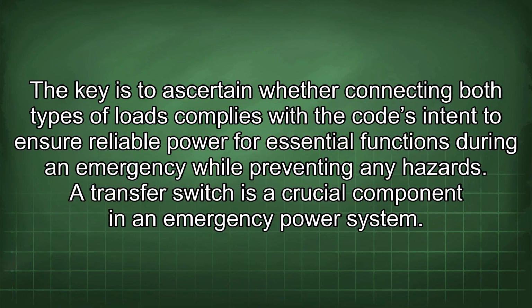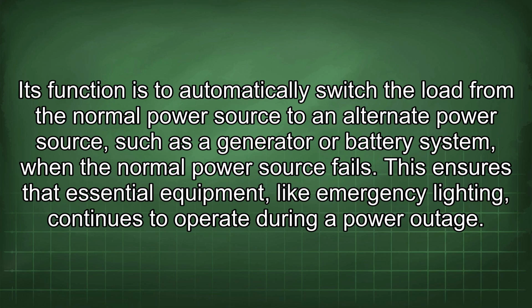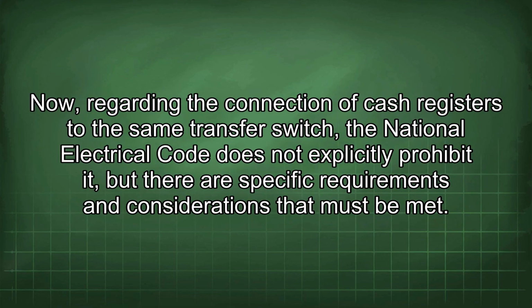A transfer switch is a crucial component in an emergency power system. Its function is to automatically switch the load from the normal power source to an alternate power source, such as a generator or battery system, when the normal power source fails. This ensures that essential equipment, like emergency lighting, continues to operate during a power outage. Now, regarding the connection of cash registers to the same transfer switch, the National Electrical Code does not explicitly prohibit it, but there are specific requirements and considerations that must be met.